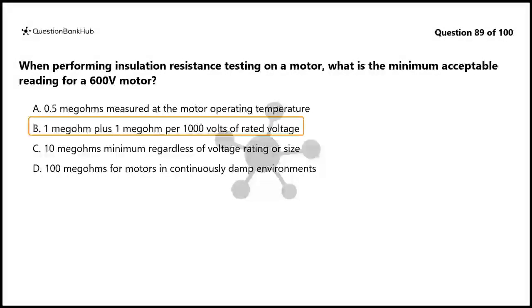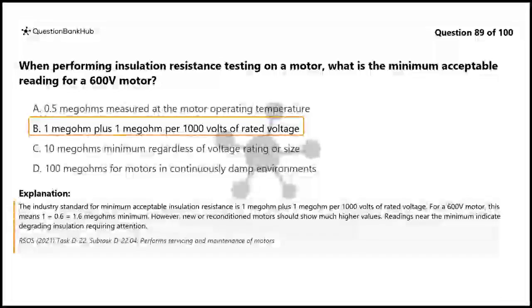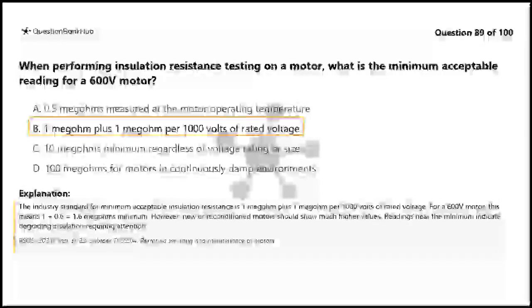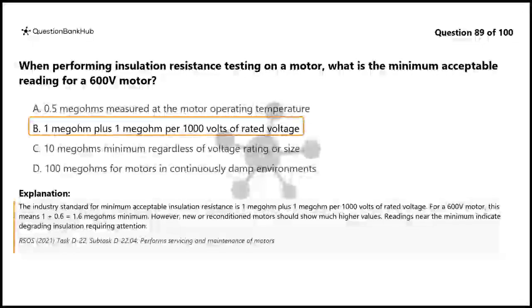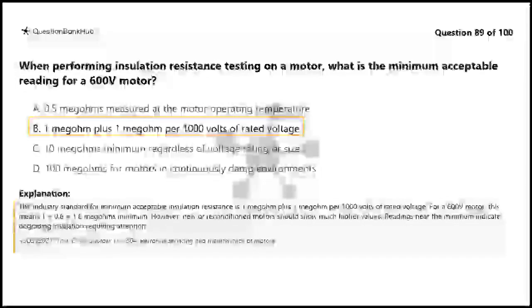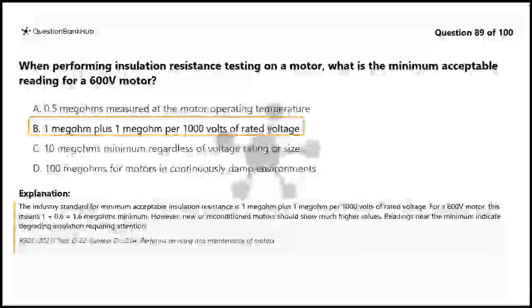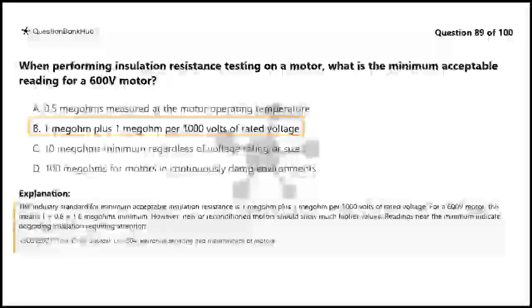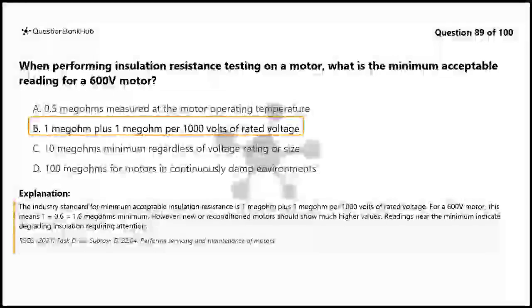The correct answer is B, 1 megohm plus 1 megohm per 1000 volts of rated voltage. The industry standard for minimum acceptable insulation resistance is 1 megohm plus 1 megohm per 1000 volts of rated voltage. For a 600 volt motor, this means 1 plus 0.6 is equal to 1.6 megohms minimum. However, new or reconditioned motors should show much higher values. Readings near the minimum indicate degrading insulation requiring attention.